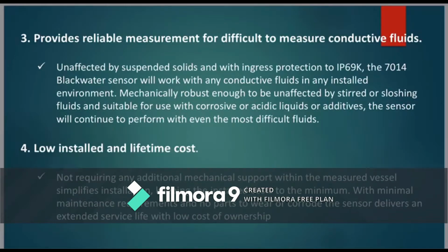Third one, provides reliable measurement for difficult to measure conductive fluids. Unaffected by suspended solid and with ingress protection to IP69K, the 7014 Blackwater sensor will work with any conductive fluids in any installed environment. Mechanically robust enough to be unaffected by stirred or sloshing fluid and suitable for use with corrosive or acidic liquids or additive. The sensor will continue to perform with even the most difficult fluids.